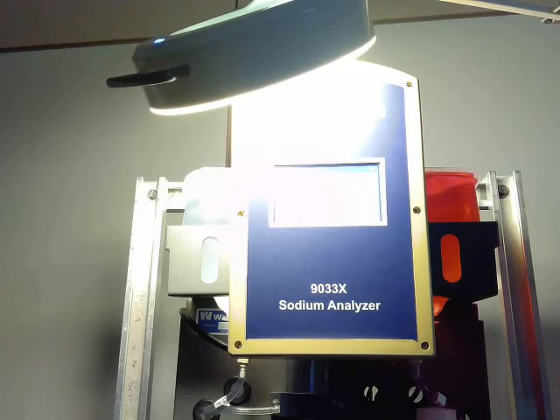One of the reasons for that is as our electrodes age, the response time tends to be the first thing that indicates that they're starting to fail. So if you have a calibration that might pass if you let it sit there for an hour in standard, that's not going to be very helpful if you start to see a high sodium event or something like that. It's going to defeat the purpose of having the analyzer if you have a slow response. So again, it's based on time. It's not looking for a certain number.